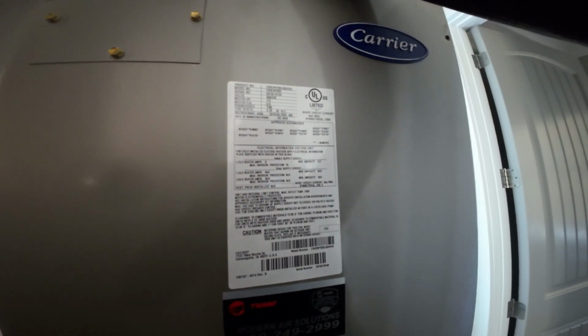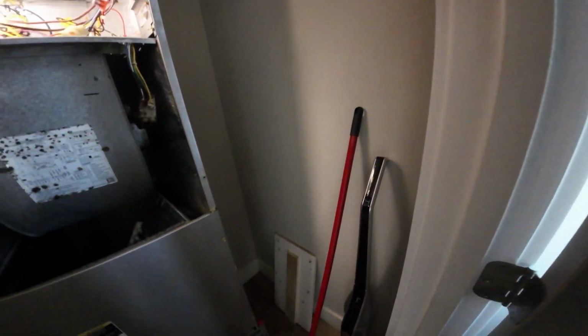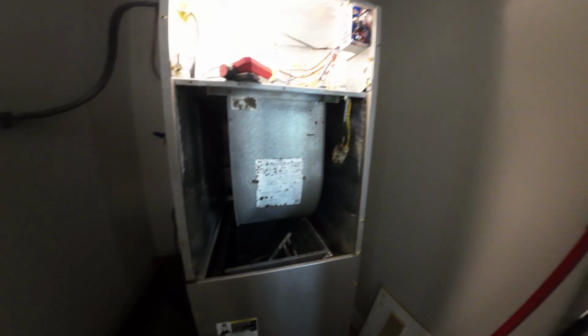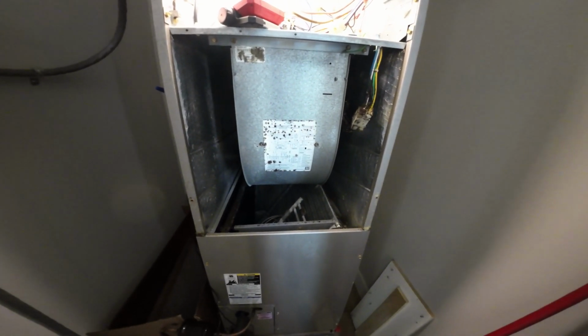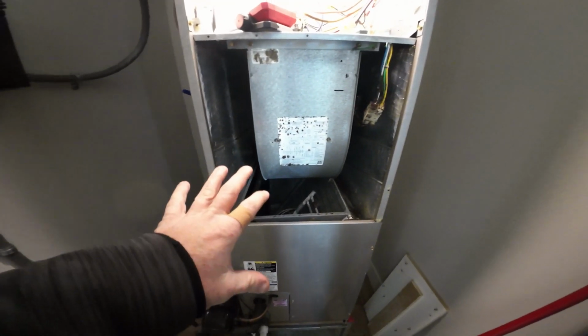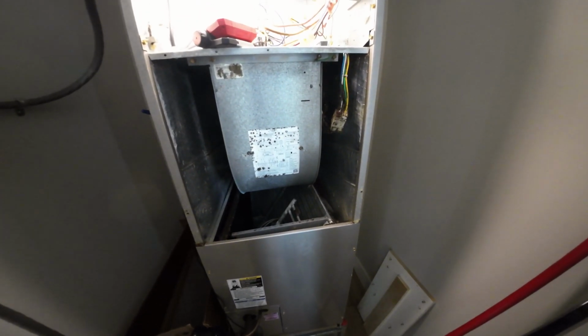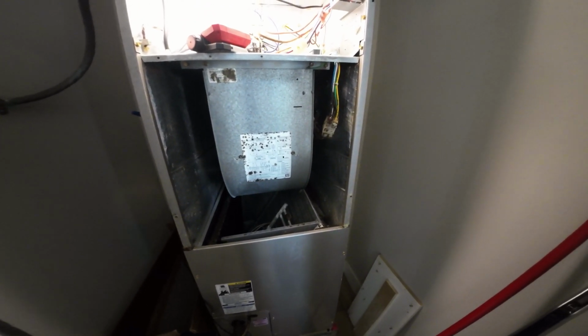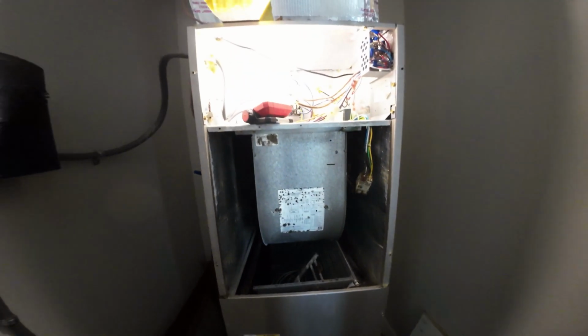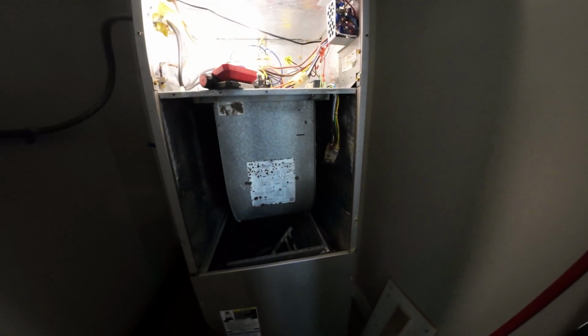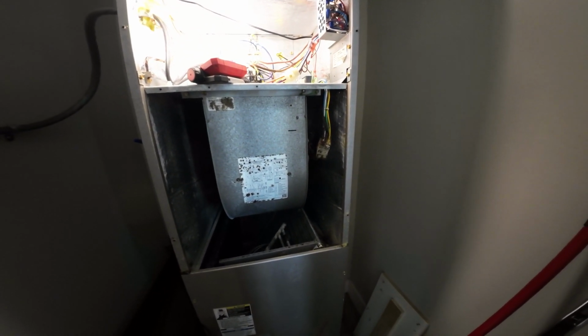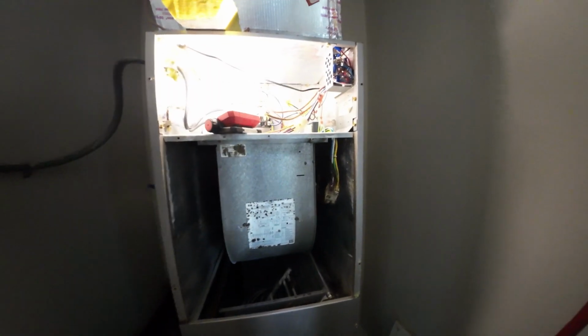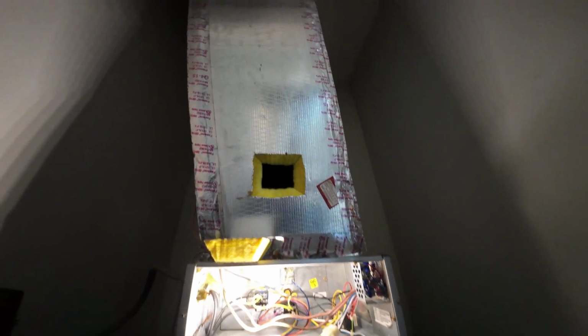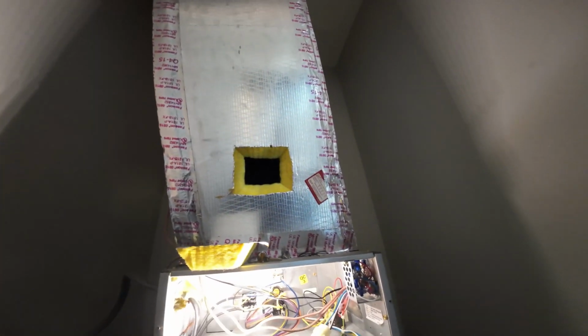This system has been installed since 2015, almost 10 years old. So to me, that's not terrible mold growth for a 10-year-old system. It's been here for 10 years, and that's not terrible mold growth at all. So I'm just going to recommend a maintenance cleaning here, and maybe a UV light to maintain at the ductwork.